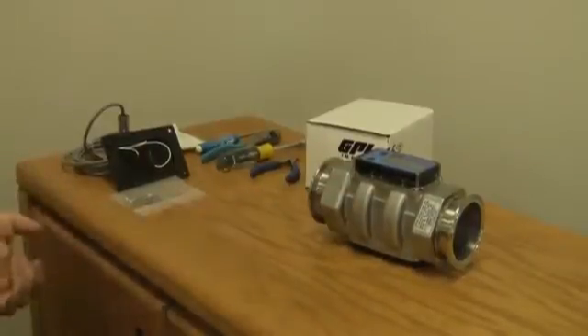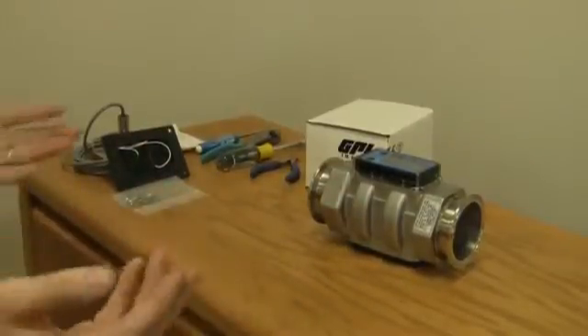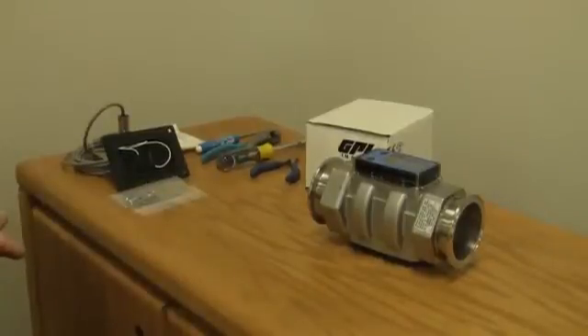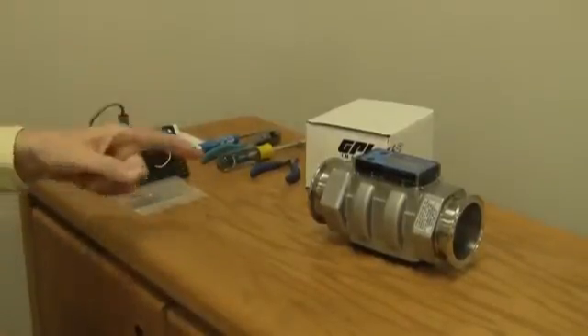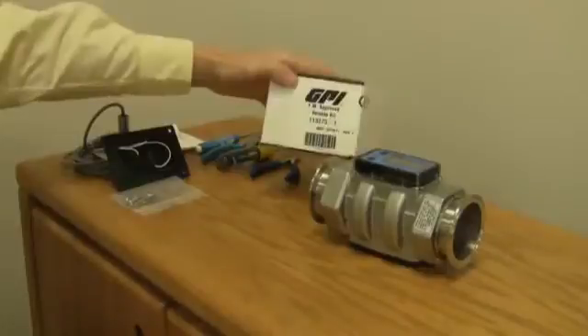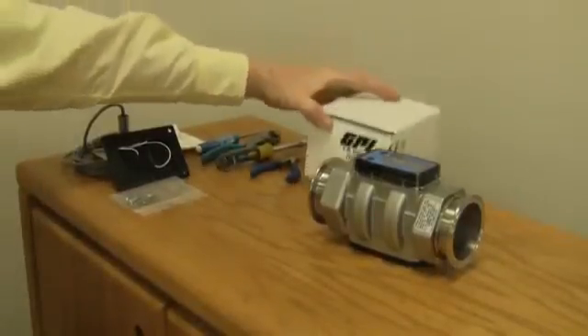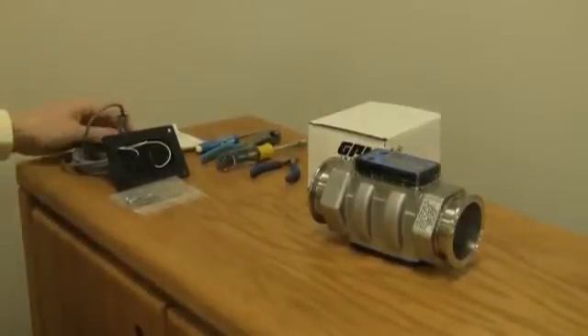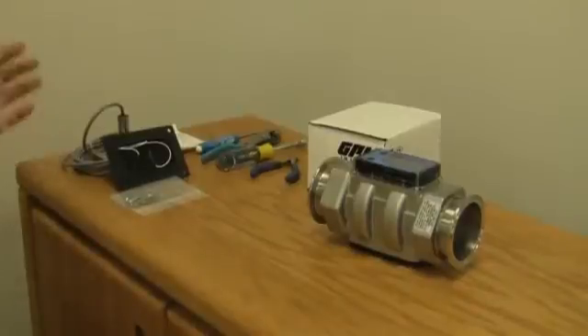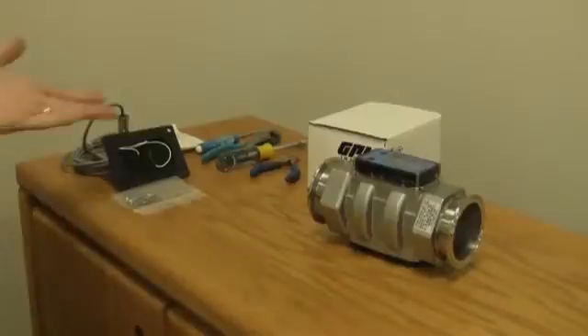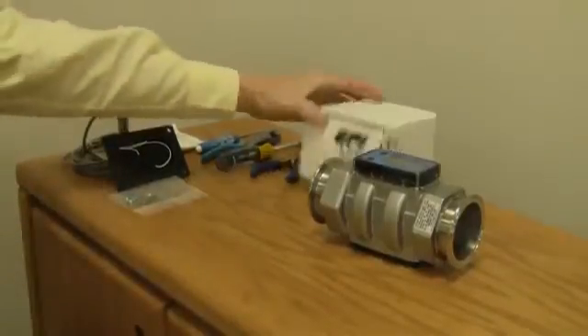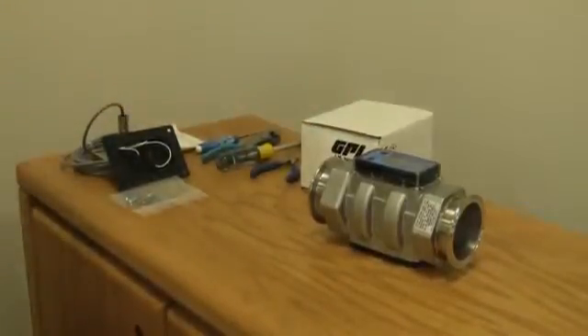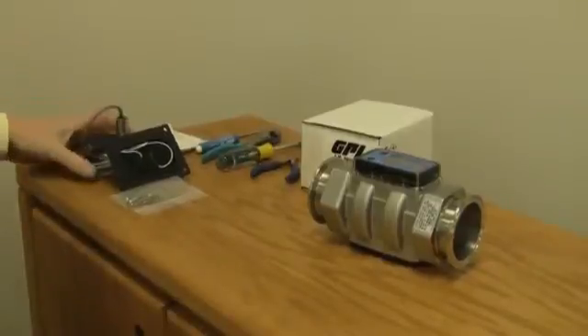What does FM approved mean? Well, this is an intrinsically safe or explosion proof display as is. If you take the display off or you add other accessories to it you lose that, but if you wanted to remotely mount the display and you use the FM approved remote kit then you can keep that FM approval. Now keep in mind that if you use a standard remote kit, which again there's a little bit of difference and I will show you the difference later, you cannot do that. So that's one of the reasons I really like the FM approved kit much better.